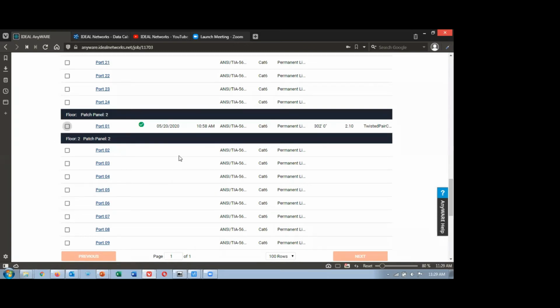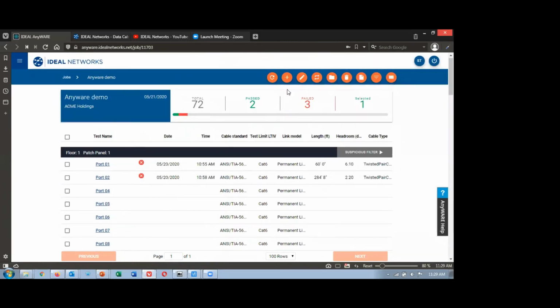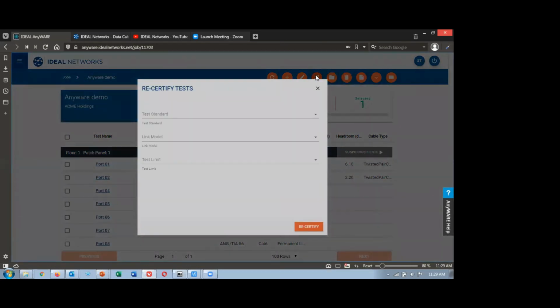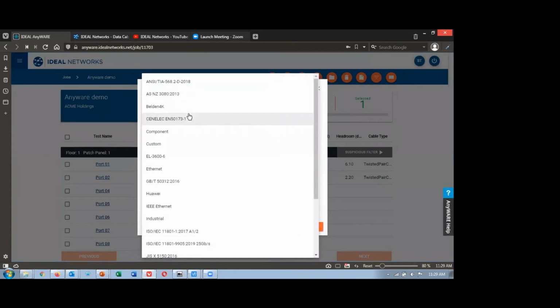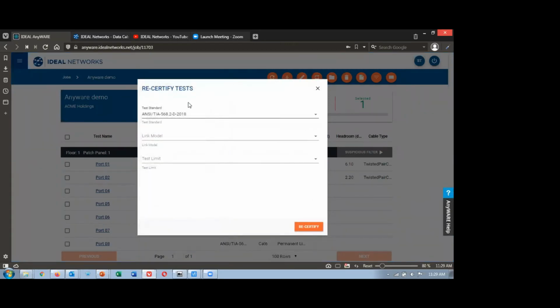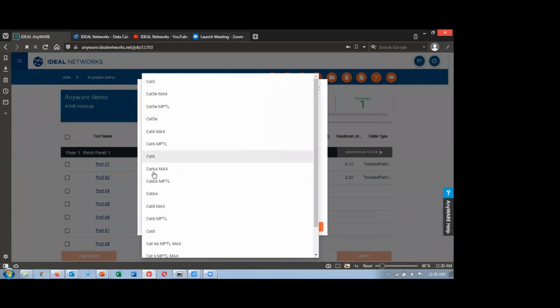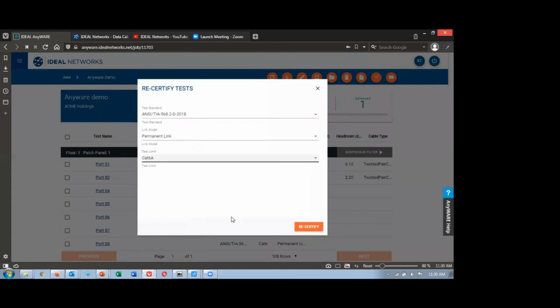If that job was truly supposed to be certified to category 6A, I can just hit a tick mark there, go back up to the top where we've got these two arrows chasing each other, hit that button, and it asks what I want to recertify this as. So, North America, typically ANSI TIA, permanent link, and we'll certify this to a Cat 6A standard.